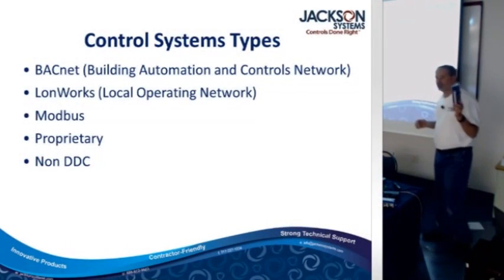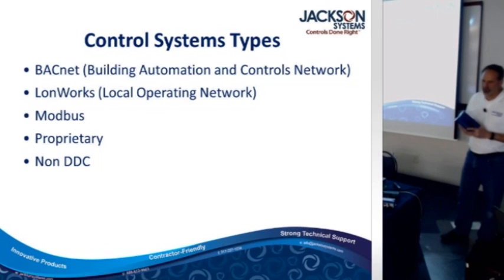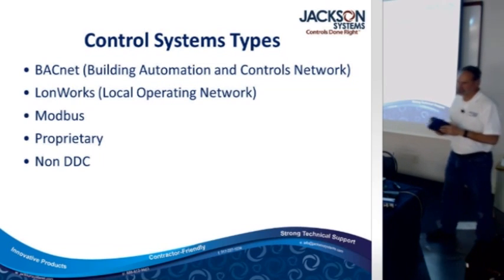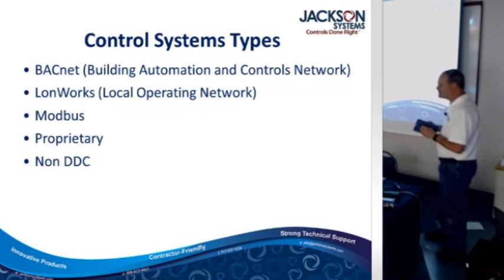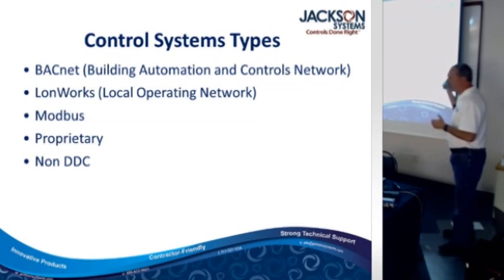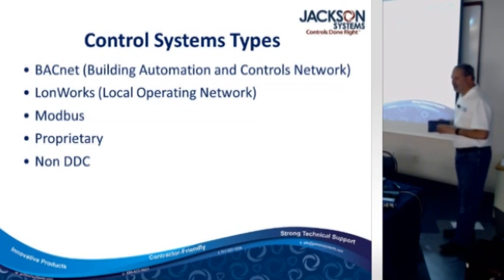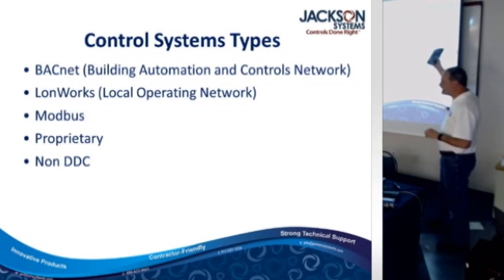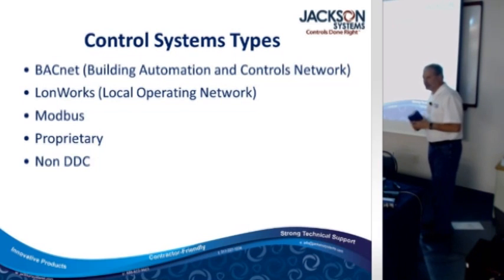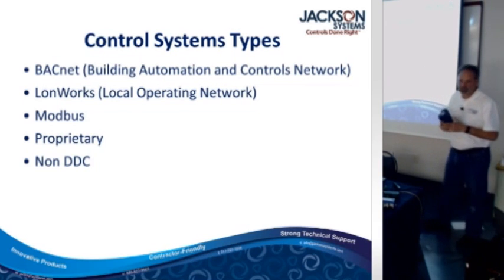In my opinion, Lon is much more robust. If we hook up a Lon network, when we go to start communicating with stuff, it's just going to work. It just always does. BACnet seems to be a little more temperamental. So because of those reasons, I personally like Lon. But the reality is that BACnet is supported by ASHRAE and probably is going to win in the United States.